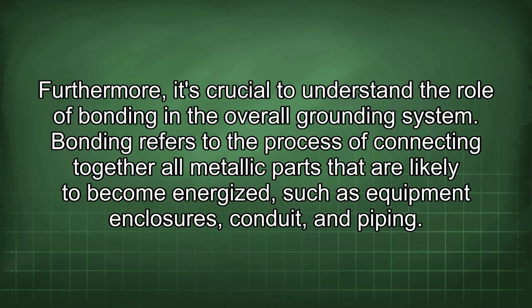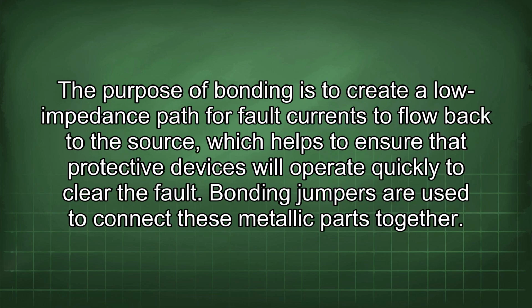Furthermore, it's crucial to understand the role of bonding in the overall grounding system. Bonding refers to the process of connecting together all metallic parts that are likely to become energized, such as equipment enclosures, conduit, and piping. The purpose of bonding is to create a low impedance path for fault currents to flow back to the source, which helps to ensure that protective devices will operate quickly to clear the fault.